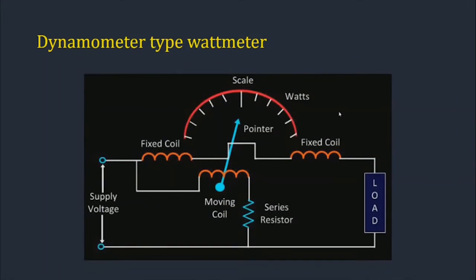The construction and working of the dynamometer type wattmeter: there are two fixed coils and a moving coil that is free to move inside the space provided by the two fixed coils. The fixed coils are wound with thick wires and the moving coil is wound with thin wires. The flux produced by the fixed coils is proportional to the current through the load, and the flux produced by the moving coil is proportional to the voltage across the load. The interaction of fluxes causes a reading in watts.